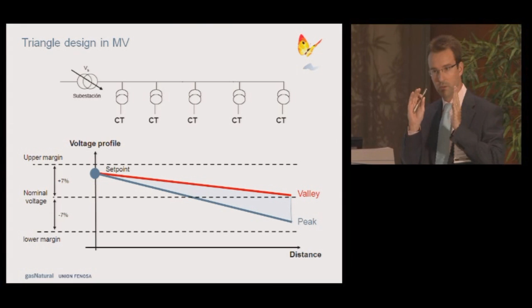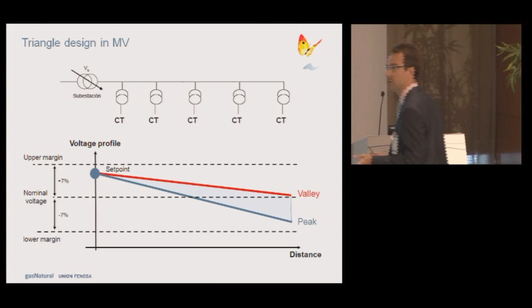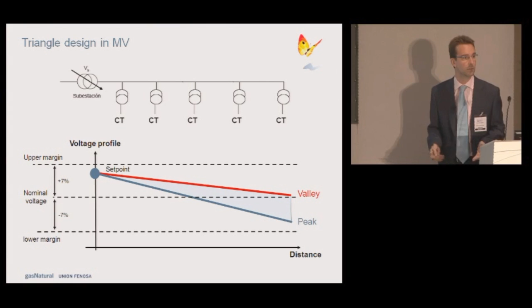We fix a set point, then analyze the scenarios in terms of valley demand and peak demand. This gives us the voltage triangle, meaning all the possible voltages the customers are going to have. We have to ensure these voltages stay within the legal range, which in Spain is a margin of 7%, upper and lower.